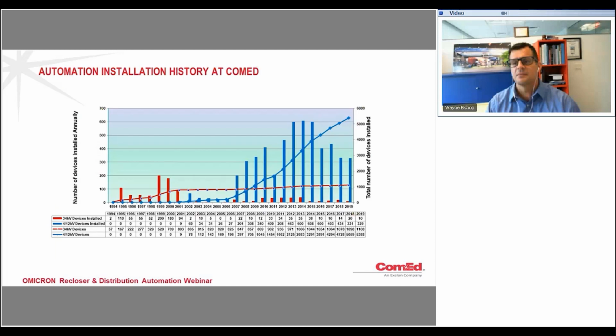In this next slide, you can see a history and progression of our DA installations. Starting from 1994 to now in 2019, we have about 5,400 DA devices on our 4 or 12 kV systems, and along with that, about 1,100 devices on our 34 kV system. I also want to note that we will be continuing to ramp up DA installations for the foreseeable future.